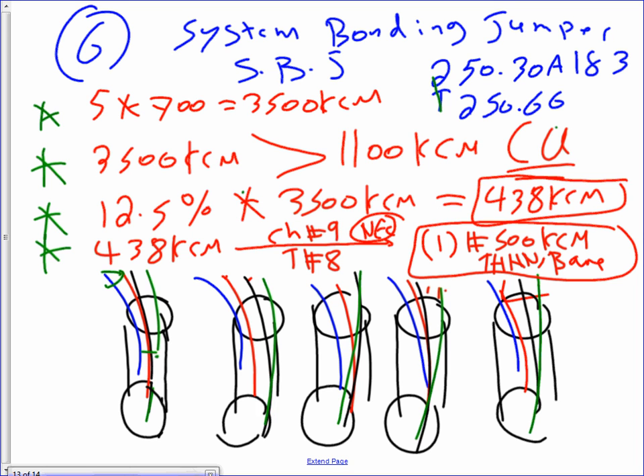Now your system will look something like this. Can you guys see the secondary system? 1, 2, 3, 4, 5 conduits, right? 5 conduits. I want to quickly remind you guys that these conductors here will be, what did we say the conductors here? 700 kcm. The neutral would be, what did we say the neutral came up to be? Was it 500? The neutral came up to be 400 kcm.